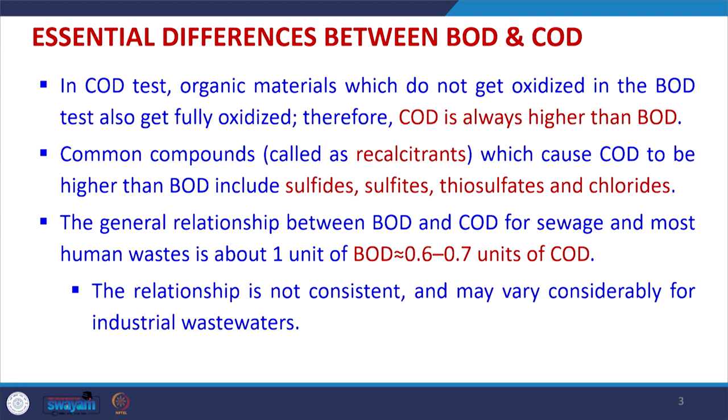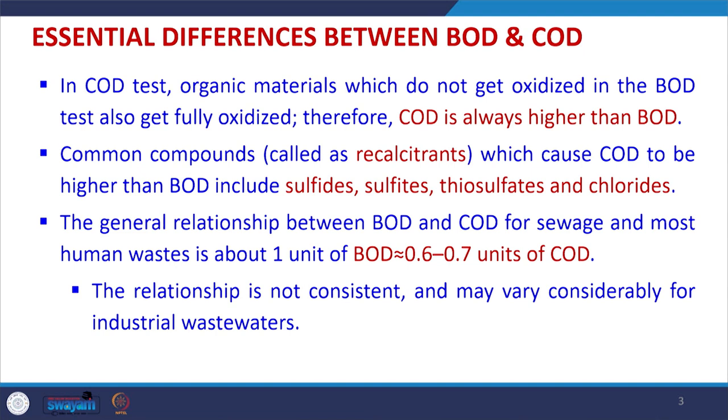The BOD/COD relationship is not constant and may vary considerably with industrial wastewater. Determining the BOD/COD ratio is very important. If the BOD/COD ratio equals 0.3, the amount of biodegradable organic matter is very low in the water sample and biological treatment is not appropriate — chemical and physicochemical treatment would be required. This low ratio represents a wastewater containing a lot of recalcitrants.